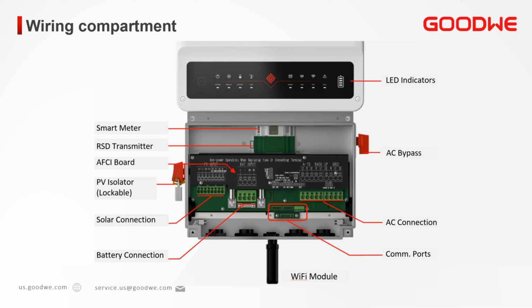First, note that you only need to open the bottom half of the enclosure. This part is the wiring compartment. It isn't necessary or recommended that you open the upper part of the inverter. The top half is the power electronics, and you could break the weather seal. The only access point is the lower part or wiring compartment.